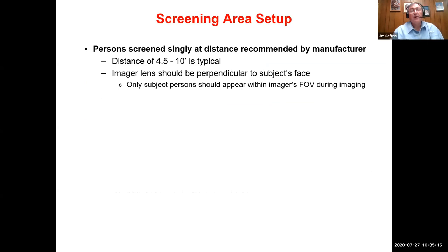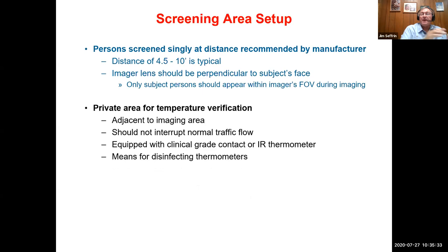Now, during screening, persons are screened singly at a distance recommended by the manufacturer. Depending upon the instrument that is chosen, this will be a distance of typically 4.5 feet up to 10 feet. This is going to depend upon the instrument and its optics. The imager lens should be perpendicular to the subject's face, and only subject persons should appear within the imager's field of view during imaging.